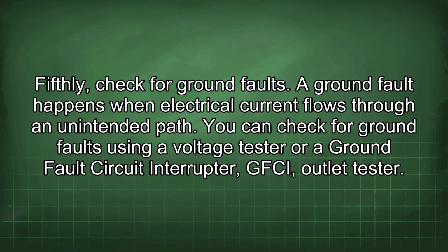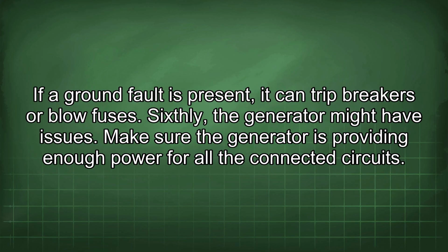Fifthly, check for ground faults. A ground fault happens when electrical current flows through an unintended path. You can check for ground faults using a voltage tester or ground fault circuit interrupter, GFCI, outlet tester. If a ground fault is present, it can trip breakers or blow fuses.